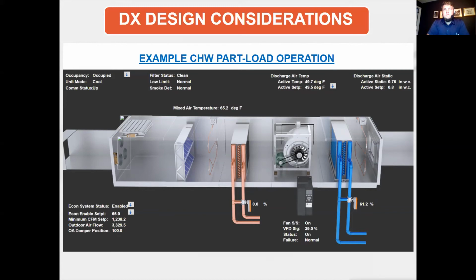And we have an ice storage system in our building that makes real cold water. So this is designed to provide 50-degree air to fan-powered boxes. So the airflow is maybe lower than you might see in some systems. But the point is that it's 65 degrees outside. The fan would heat that air up to about 67, and it wouldn't be adequate to cool the building. So what we had going on yesterday, looks like we had 3,300 CFM being delivered to the boxes, and the coil was cooling the air down to 50 degrees, which was the design. And it was probably doing it just strictly off the ice. The compressors probably weren't even running at that point.